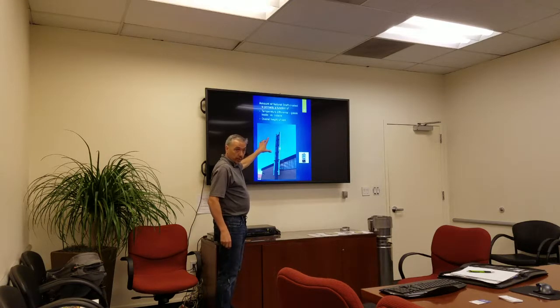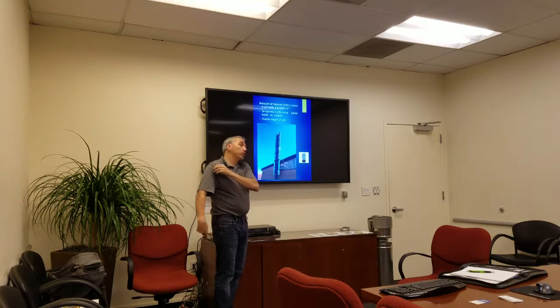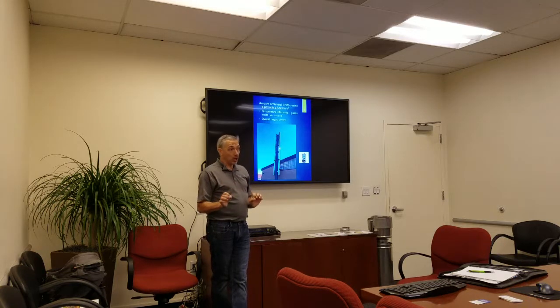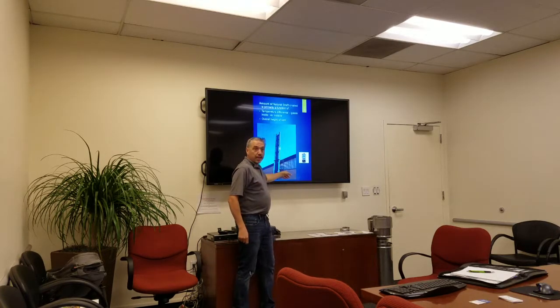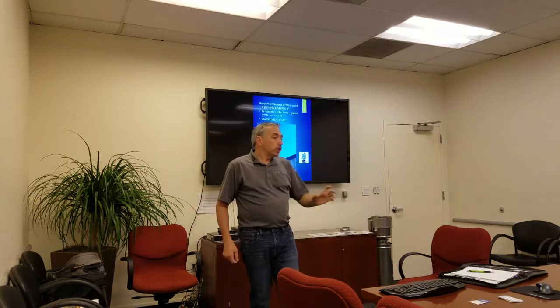The height can affect the draft. A short stack doesn't have very much draft, and this draft is measurable. If we put a manometer — either digital, fluid-filled, or some type of way to measure differential pressure — generally in inches of water column, we can measure the difference between the surrounding environment and the point of entry at the boiler, and we call that draft. It's measurable — typically 0.3 to 0.4 inches water column.